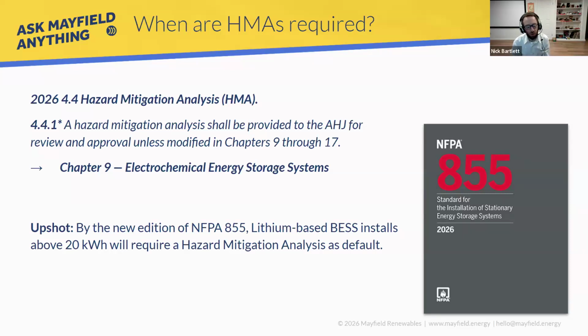Yeah, sure. So the 2023 NFPA 855 had a maximum allowable quantity trigger threshold of 600 kilowatt hours, which was a relatively arbitrary number. I don't represent the NFPA technical committee, but from the discussions that occurred, it was understood that you can have a serious incident in an energy storage system that's 598 kilowatt hours. You can have a very significant explosion, or multiple commercial and industrial units next to each other resulting in a significant fire.